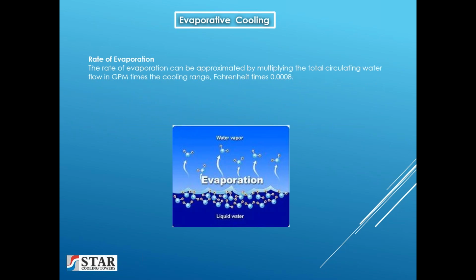So when we talk about a small amount of water that's evaporated to get this cooling effect, the approximate formula is that the rate of evaporation can be approximated by multiplying the total circulating water flow in GPM times the cooling range in Fahrenheit times 0.0008. So in our example, if we assume that we were circulating 10,000 gallons per minute at the 15 degree Fahrenheit range, which is the 85 to 70, times the 0.0008, we see that we were losing 120 gallons per minute to evaporation.